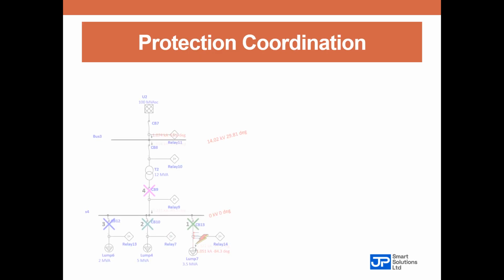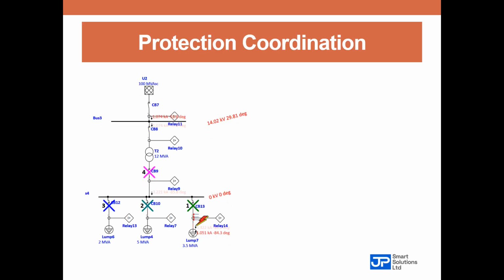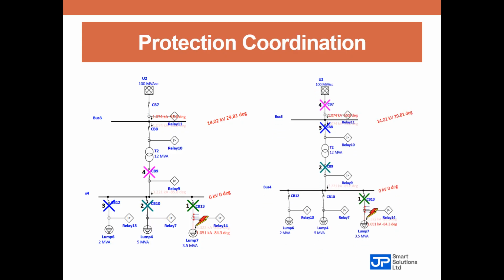So let's look at this. Now we have this first system over here, and we have the same system on the right. We have different sequences of operation. We have relays on each breaker. Now, the fault is placed on lump 7, which is load number 7 over here. The fault is also placed on load number 7 over here. This axis illustrates the tripping sequence of the system. So the fault occurred on lump 7 and circuit breaker 13 was the first to open. The second to open is circuit breaker 10, the third is circuit breaker 12, and the fourth is circuit breaker 9. This is for this system.